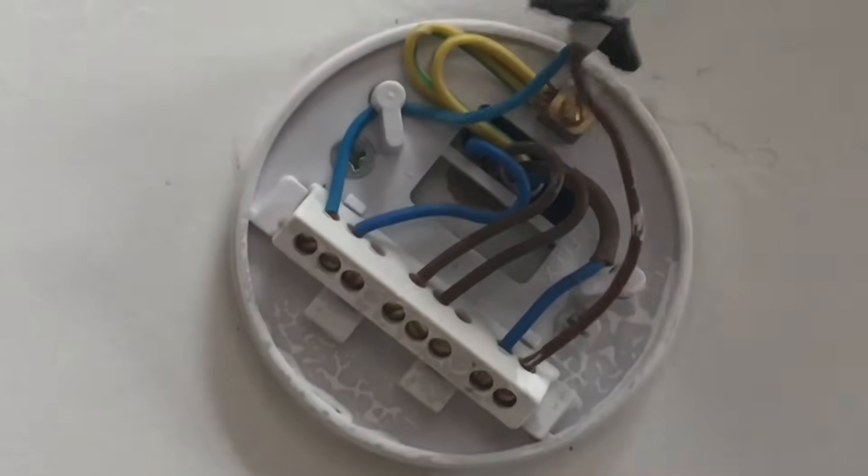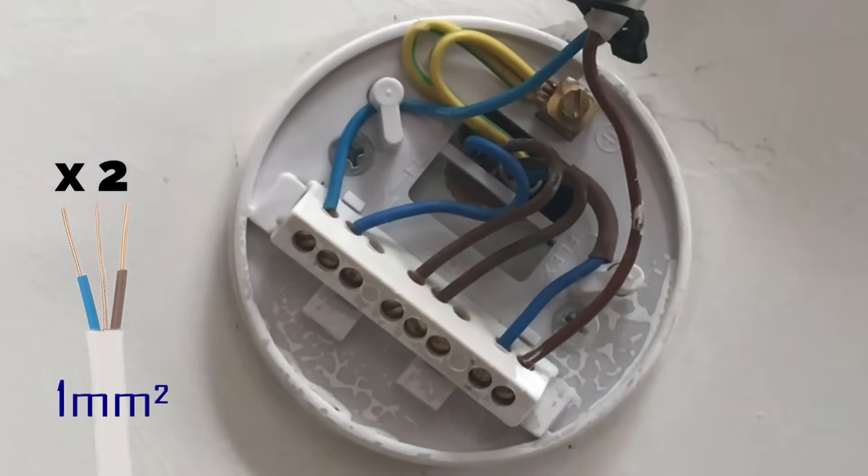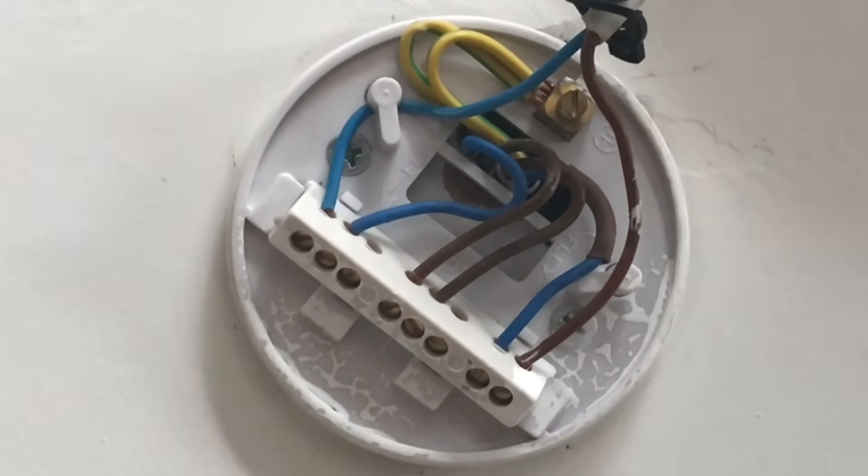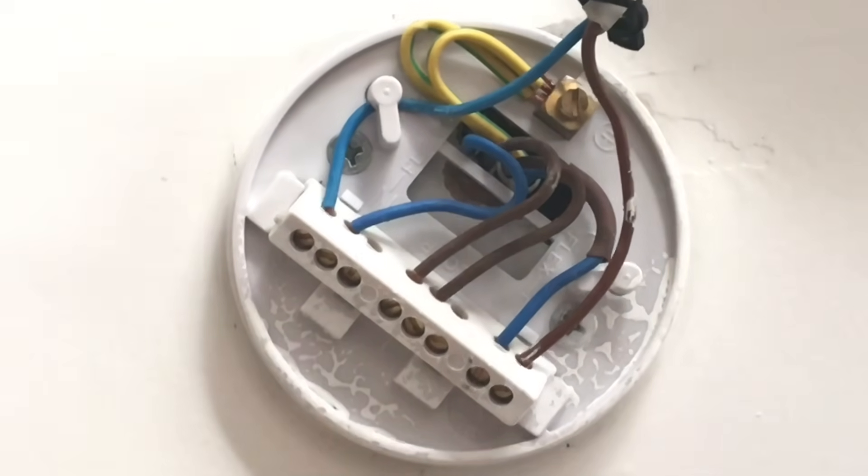So this time we only have two one millimetre squared twin and CPC cables coming into this fitting. The reason for that it is the final point on the radial lighting circuit and only has the supply coming in. It doesn't go off to another room.